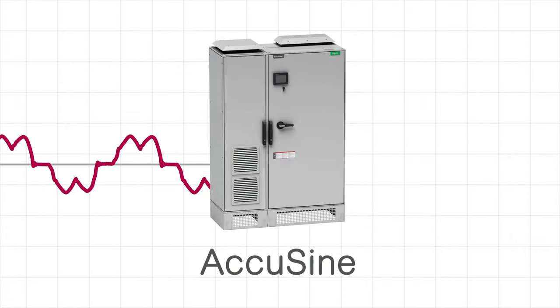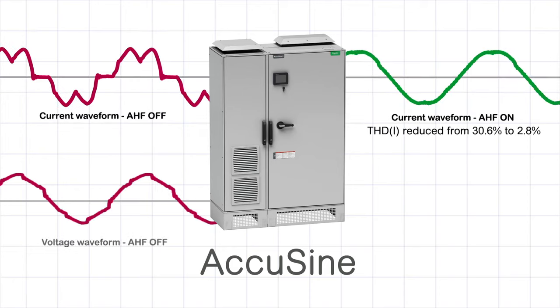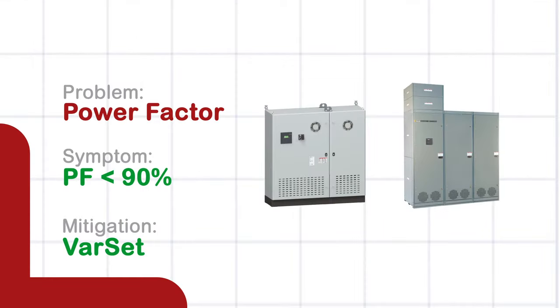AccuSine is ideal to remove the high frequency current from your distribution network, which in turn reduces the voltage distortion by stopping the flow of high frequency current through your electrical network impedance. The reduction of total harmonic distortion current and total harmonic distortion voltage removes the stress on your distribution network.